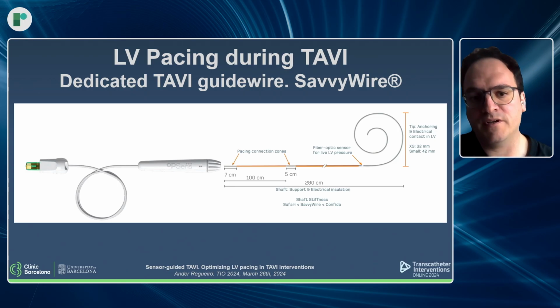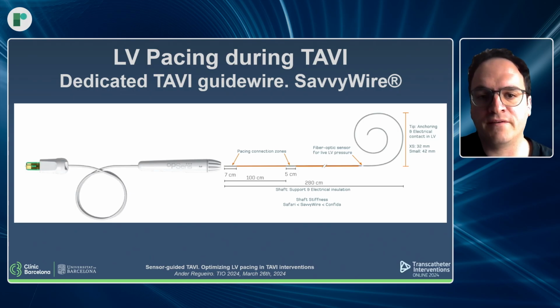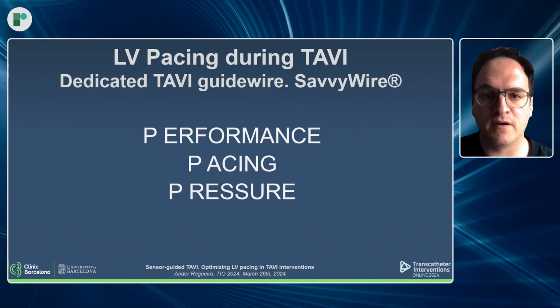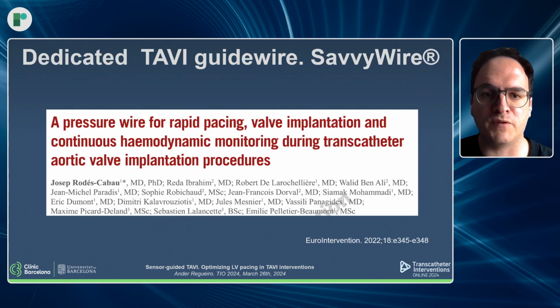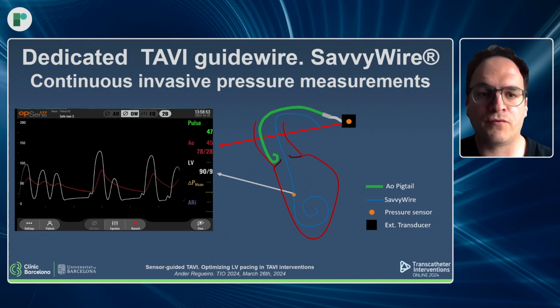Another particular characteristic of this wire is that at the end of the curve, it has a fiber optic sensor to measure live the LV pressure. This wire is intended to give you good performance, to pace the patient, and to measure the pressure during TAVI deployment.